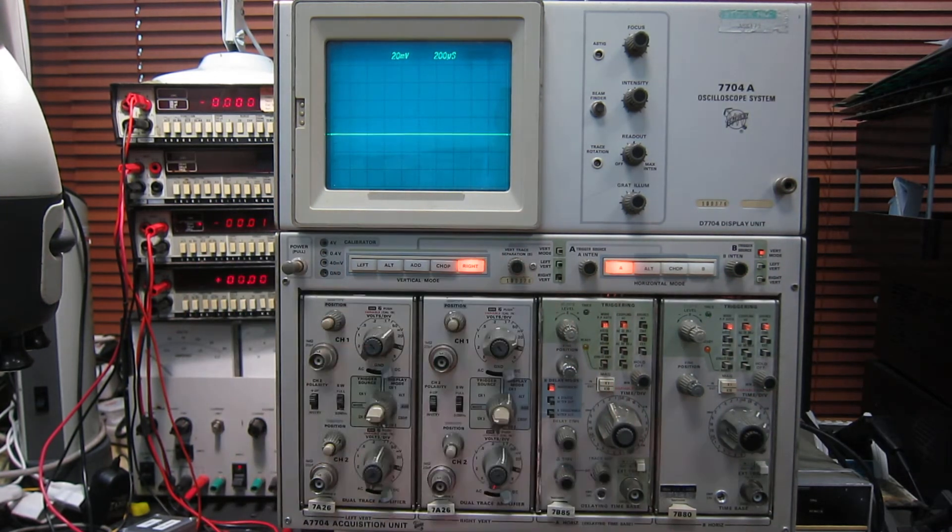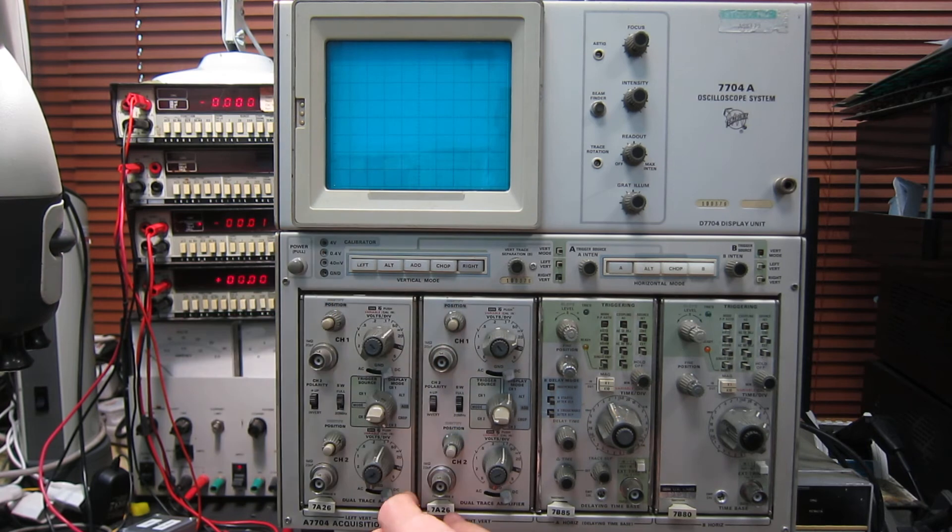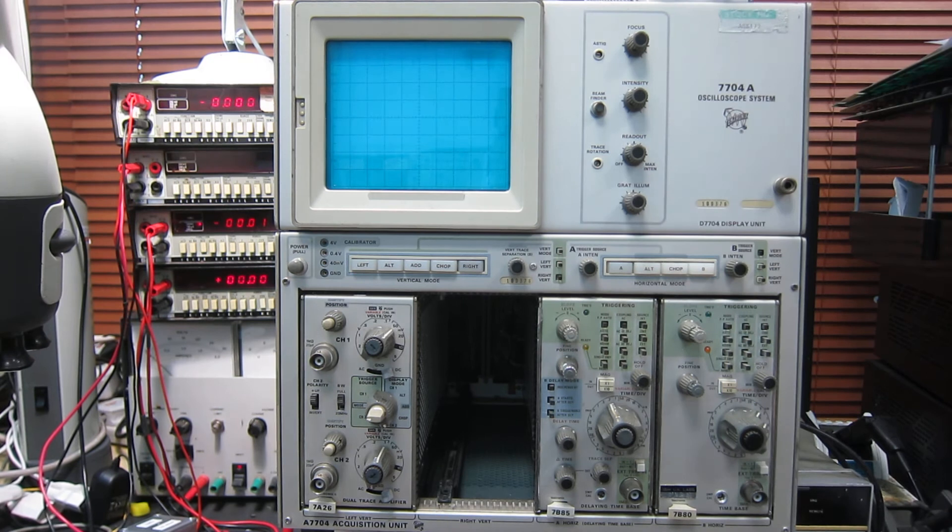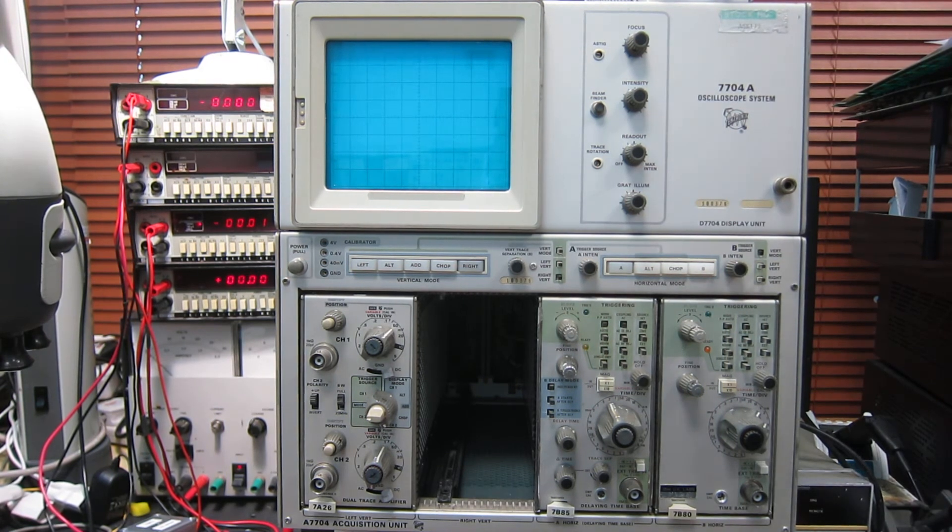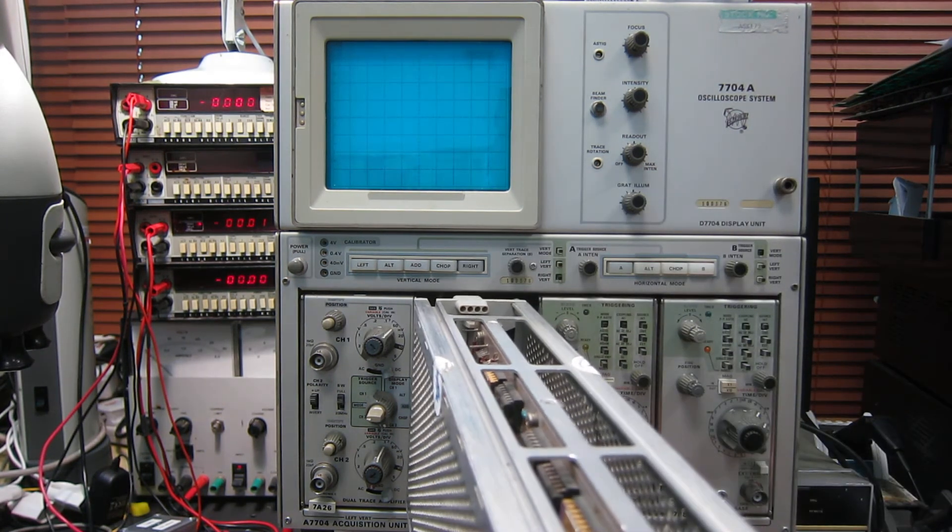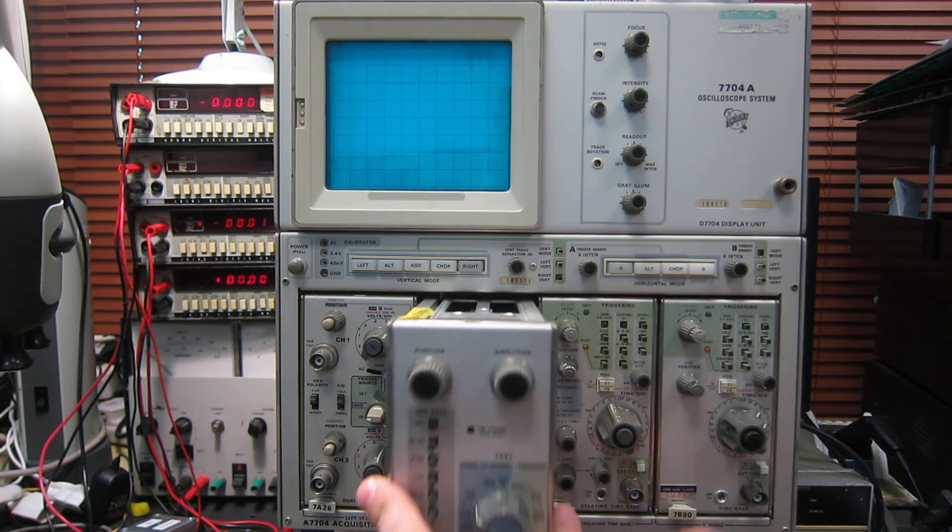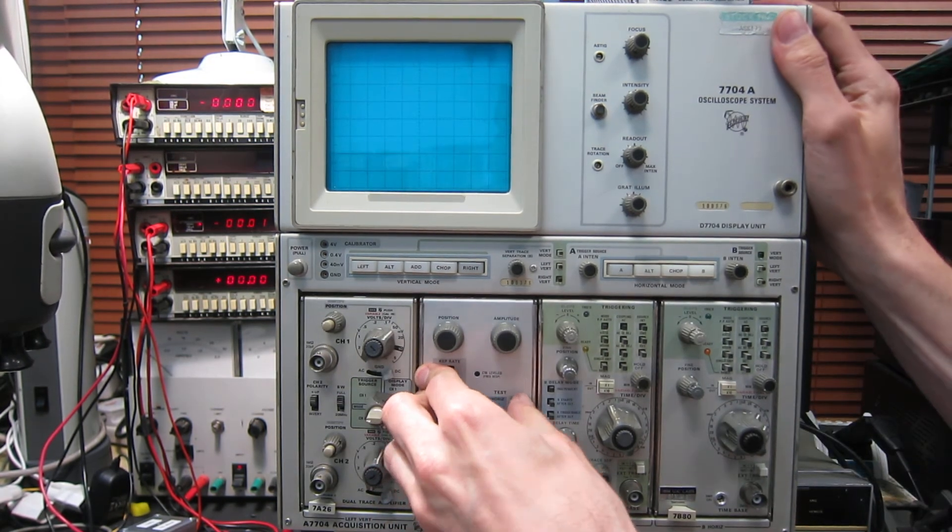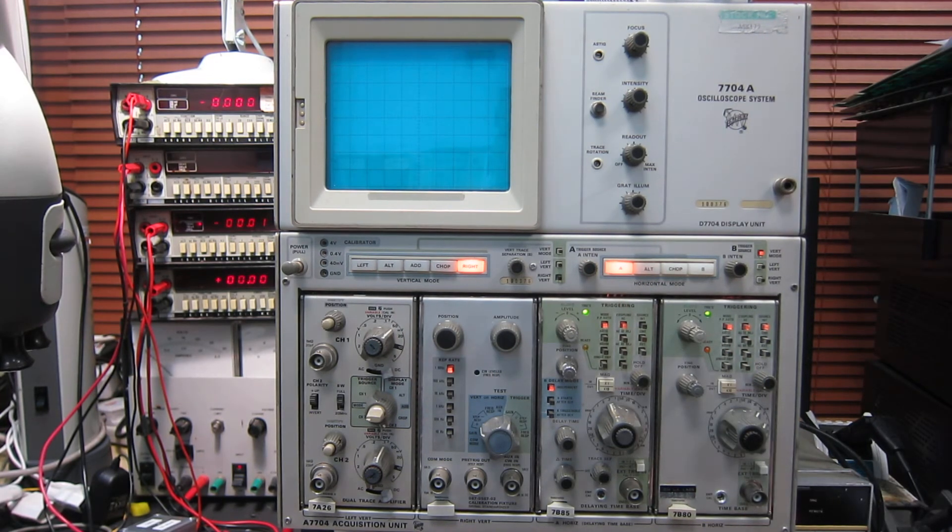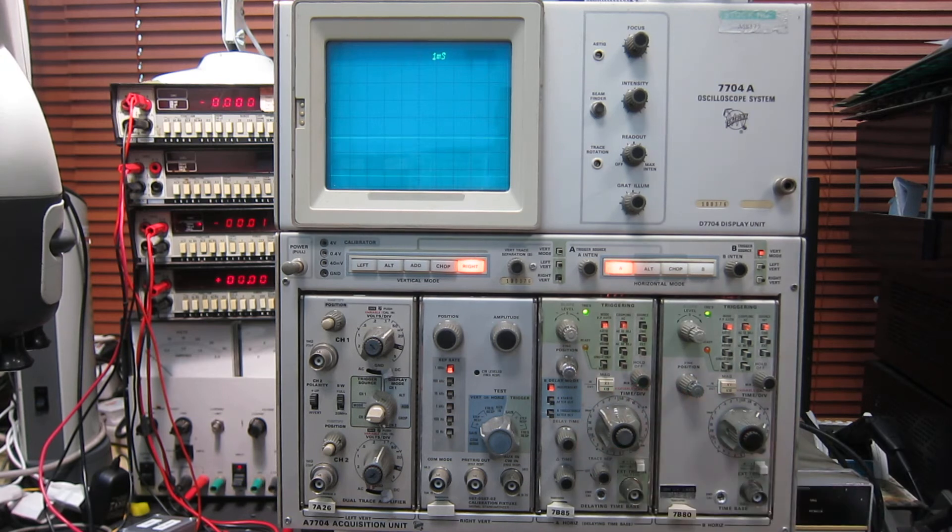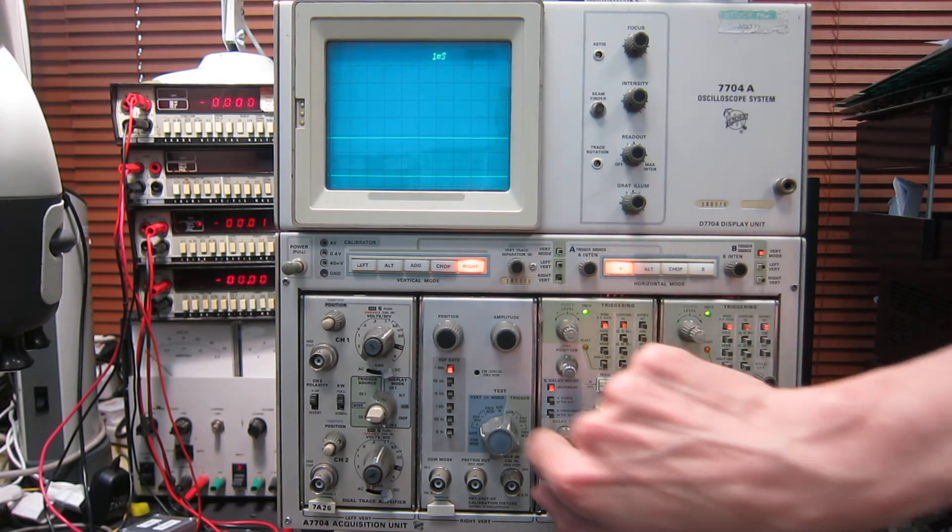If I take this probe out, I'm going to remove this vertical plug-in. And for the purposes of demonstration, I'm going to put in this, which is a Tektronix signal standardiser. It's a calibration fixture. This generates its own signals internally for testing the mainframe, so it can be done independently of the plug-ins.